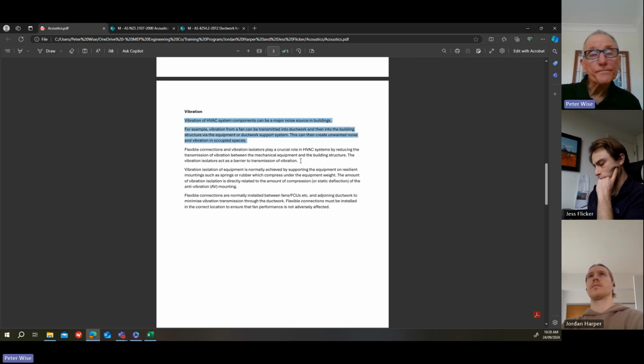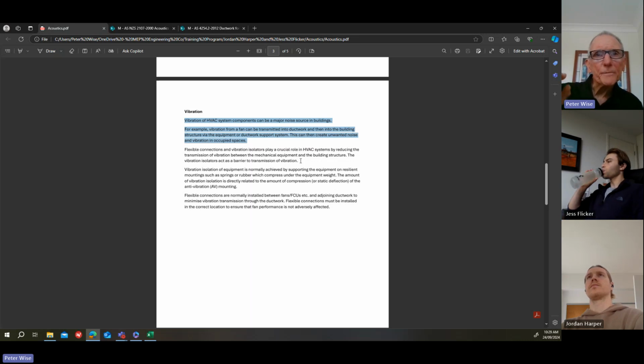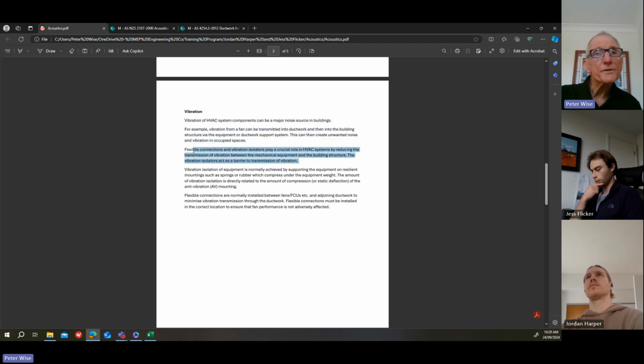That example that I mentioned before with the vibration in the floor of the office space, that was from the pipework. There's a plant room below, I think, and the pipework was fixed to the slab, but there was vibration coming through the pipework and through the slab, setting up a bit of vibration in the slab, which was then creating noise. So what we had to do was isolate the pipework from the slab by using flexible mountings, and that solved the problem. Normally you don't need to do that, but sometimes it does happen.